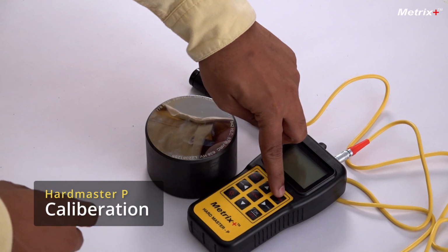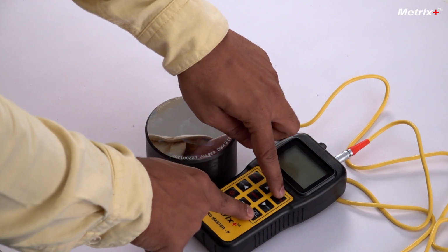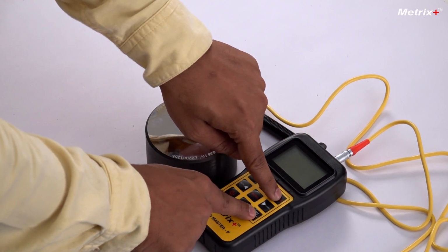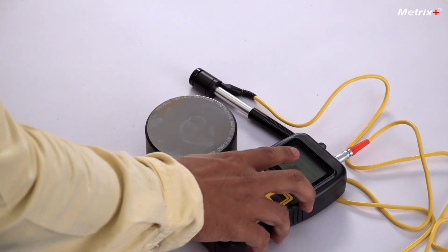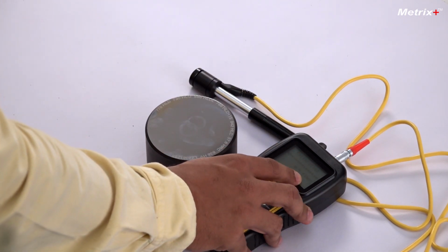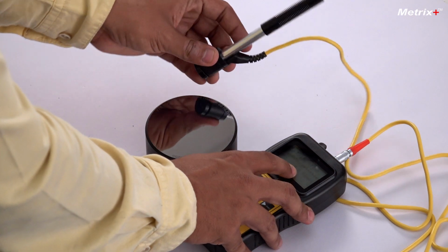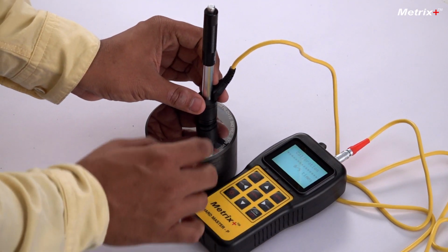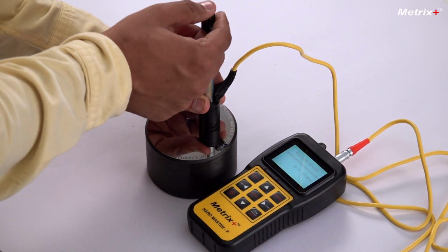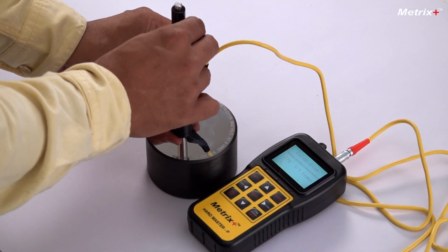Now let's look at how to calibrate this instrument if it is not giving proper values. So to go into calibration mode, press the enter and the on button simultaneously. Keep it pressed for 3 seconds and you will see the calibration mode written here. So once in this, you have to measure it 5 times. Try to measure it at different points.